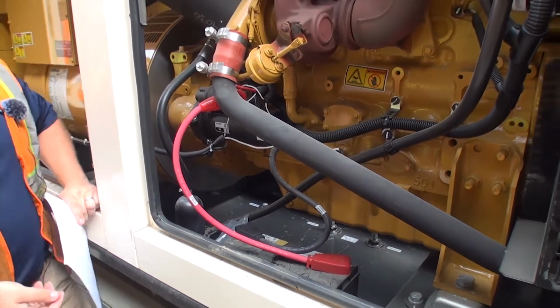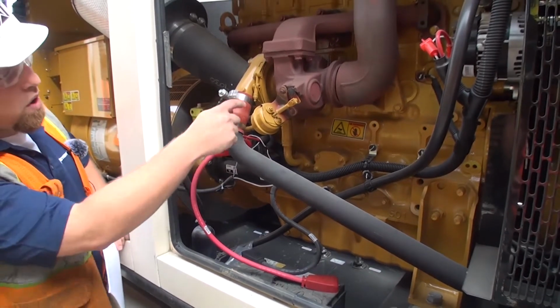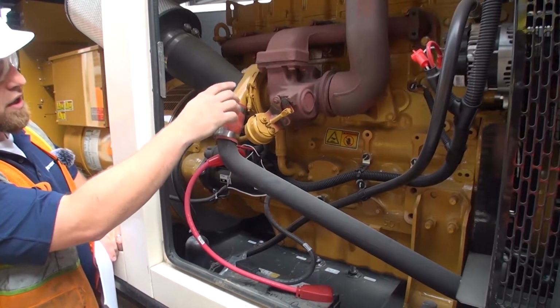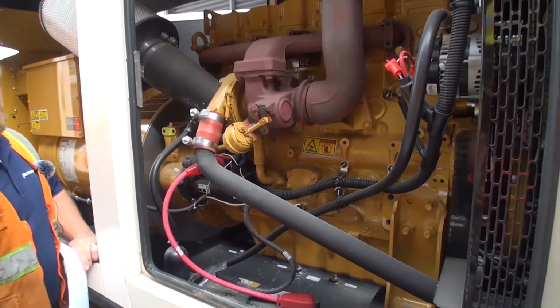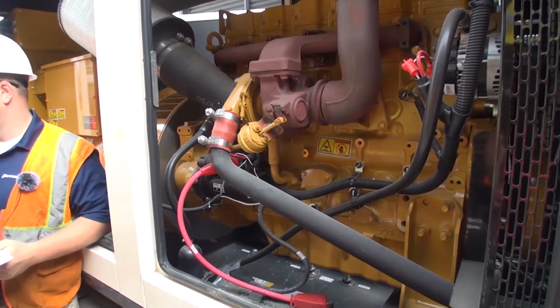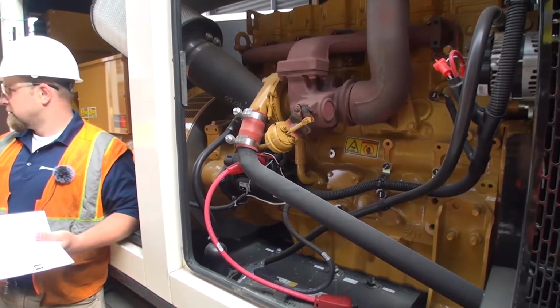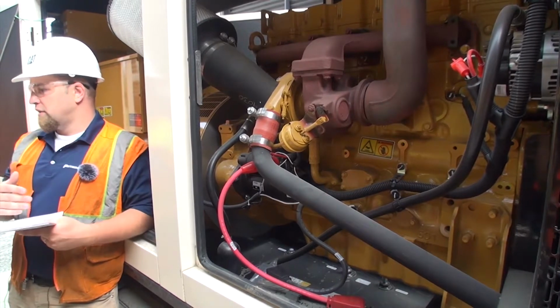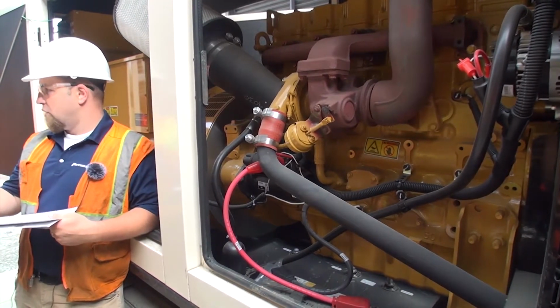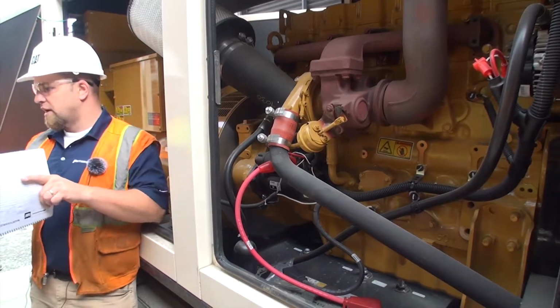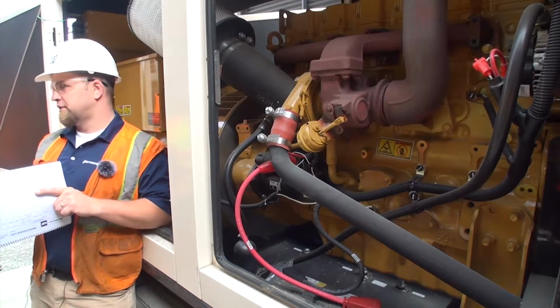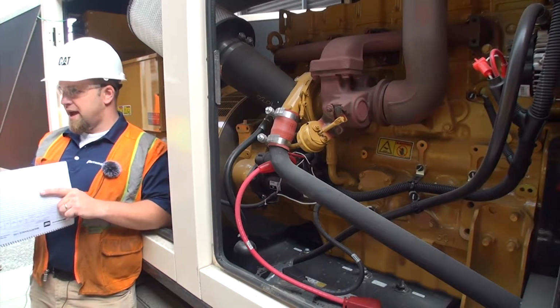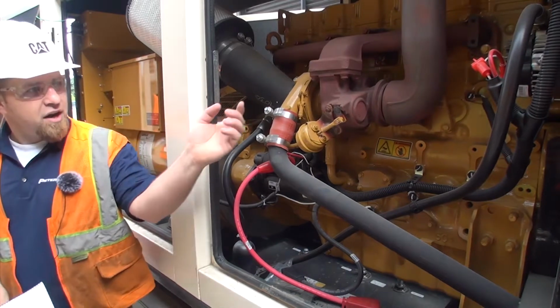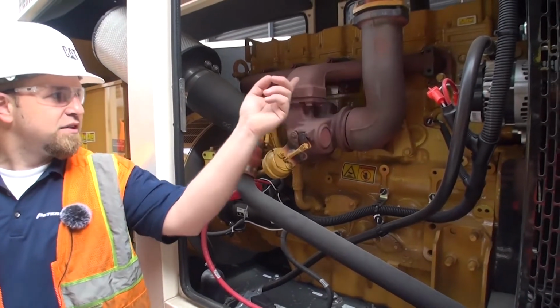Working through, you want to watch and make sure you're not getting a lot of oil or anything else coming from your headers. I don't know if you've ever heard of wet stacking - that's when you're running the unit so often without any load on it that it builds up fuel and oil inside the cylinders, and the first place you'll see that come out is the bottom side of your exhaust manifold.